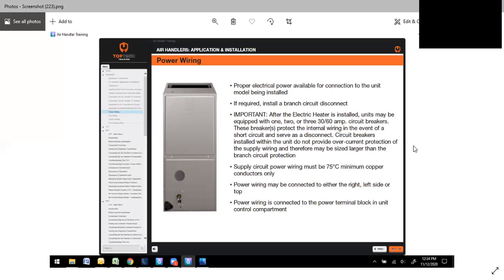The circuit breakers installed within the unit do not provide overcurrent protection of the supply wiring and therefore may be sized larger than the branch circuit protection. So it is important you use the proper sizing, make sure your connections are secure and tight. If they are not secure and they're loose, you'll actually start overheating your breakers and you'll start getting some breaker trips. Supply circuit power wiring must be 75 degrees Celsius minimum copper only. Do not use aluminum. Power wire may be connected either to the right, left, or top, whichever is convenient. Power wiring is connected to the terminal block in the unit control compartment.